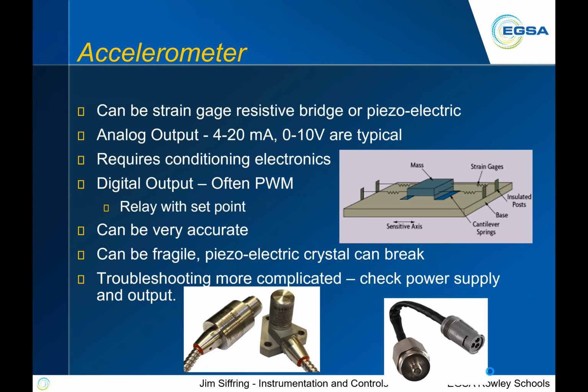Obviously, sometimes there's a set point in there. You can say, I can accept up to X amount of vibration or X amount of acceleration before I trip, and then that set point is variable. You can make these things quite accurate, but they can also be quite fragile. A piezoelectric device is basically a crystal that oscillates at a certain frequency when you apply a voltage to it, and those crystals can actually break. So they're not used a whole lot these days, but you'll see that in a lot of older equipment.